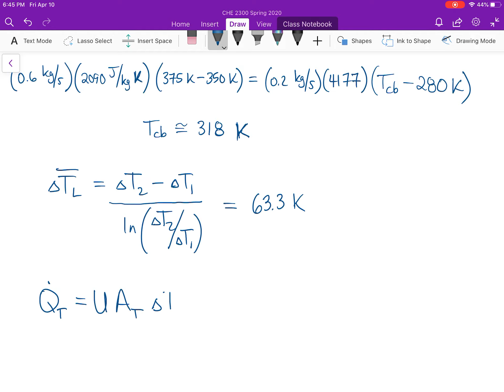For my total heat flow, I have 31,350 joules per second, which is my watts. That is equal to 250 joules per second meter squared Kelvin multiplied by the total area of heat transfer, times the log mean temperature difference of 63.3 Kelvin. If I've done my math correctly, I end up with a total area of heat transfer right around 1.98 meters squared.